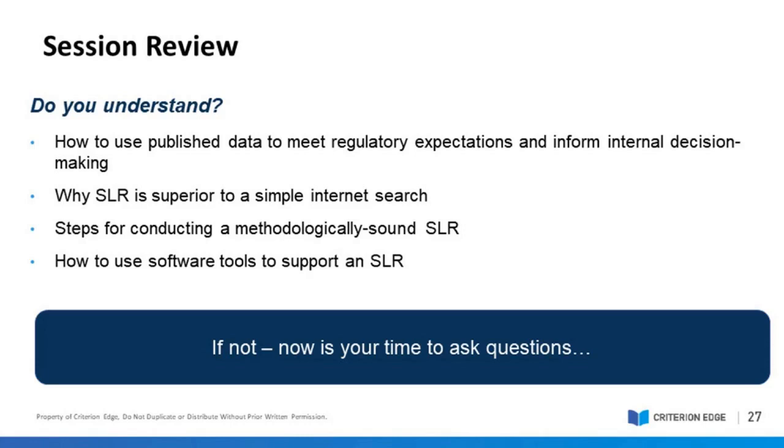But let's say that we're doing a CER revision or update, and we're doing a new literature search, and let's just say, to bring it to MDR compliance, it's a 5-year search. And again, human eyeballs are looking at these included articles, and every included article that's deemed relevant and is included gets a once over by the writer for the full text, and then that writer will summarize those full text results. That can be in tabular format or in narrative format, but they are reading every article and summarizing it.